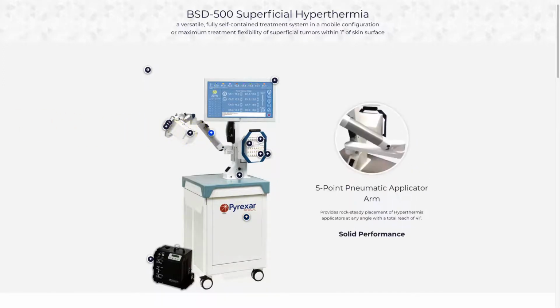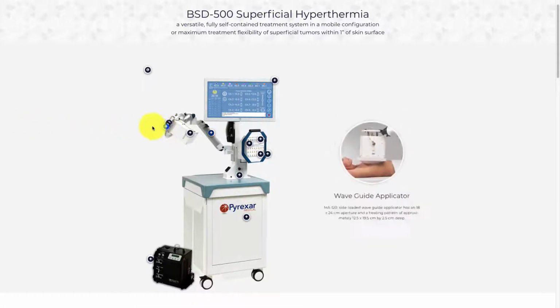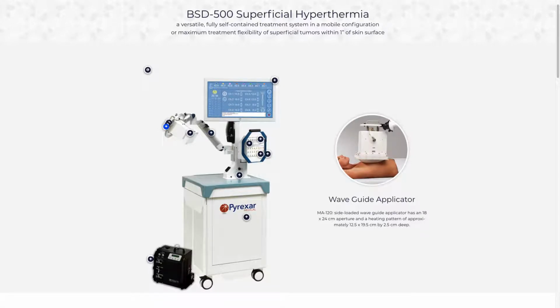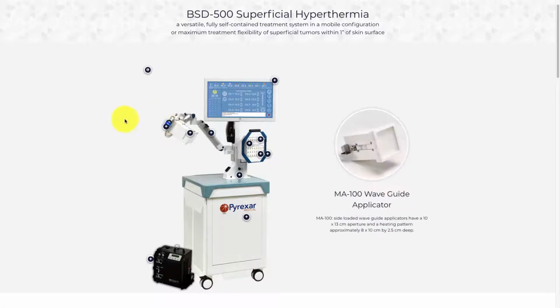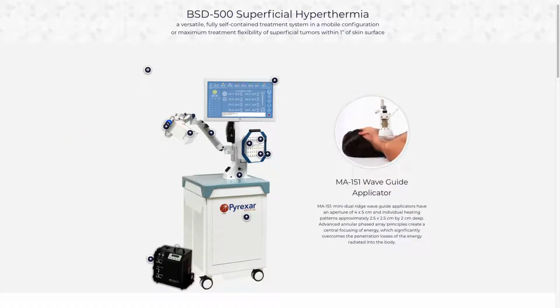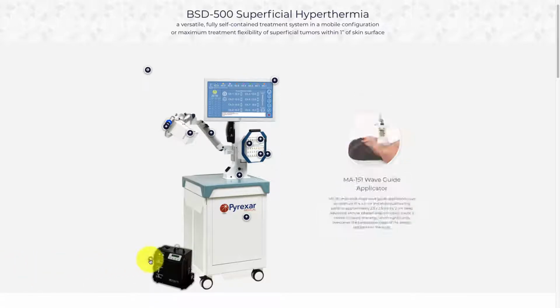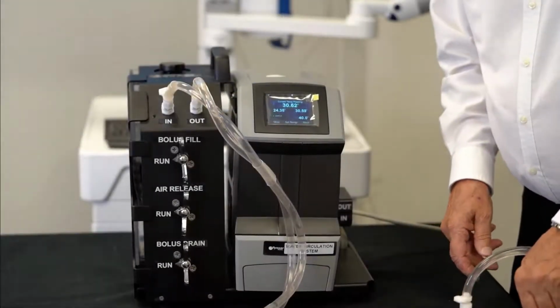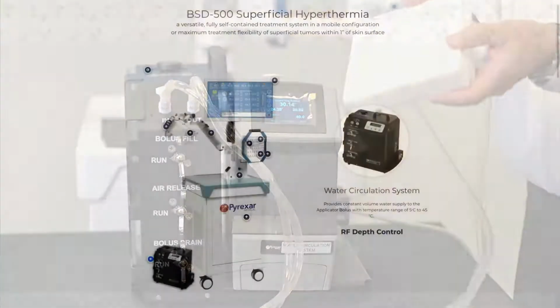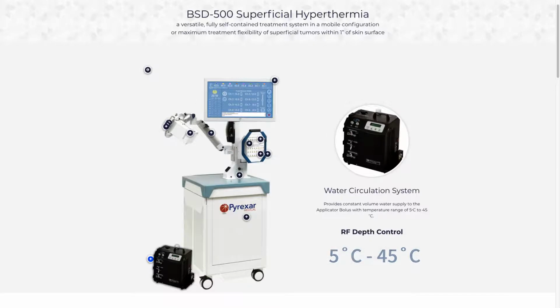A 5-point adjustable pneumatic applicator arm holds 3 different size waveguide applicators. A large format side-loaded waveguide applicator with a heating pattern of 12.5 by 19.5 centimeters, often used to treat large recurrent chest wall tumors. A medium side-loaded waveguide applicator with an 8 by 10 centimeter heating pattern, commonly used for soft tissue sarcomas and large skin lesions. And a mini dual ridge waveguide covering a treatment area of 2.5 centimeters by 2.5 centimeters, often used for head and neck cancers. The water circulation system provides constant water volume supply to the applicator bolus with a temperature control range of 5 to 45 degrees Celsius.